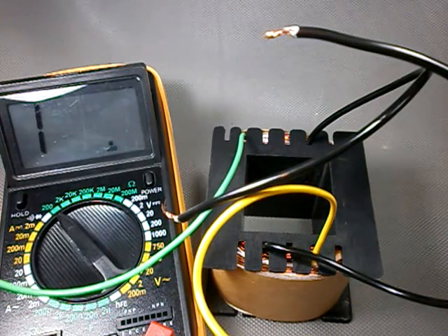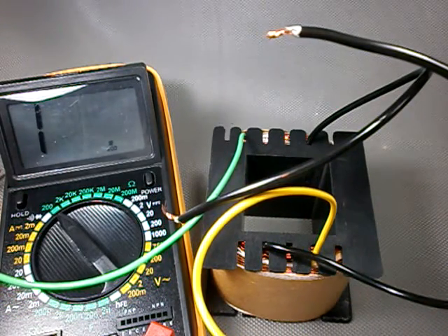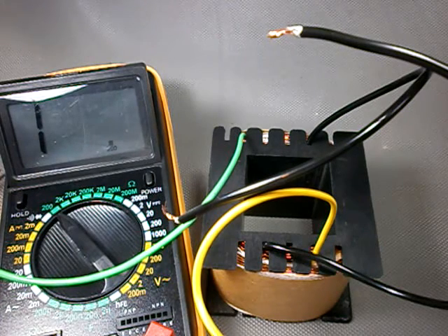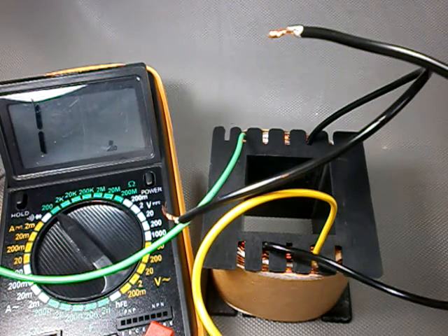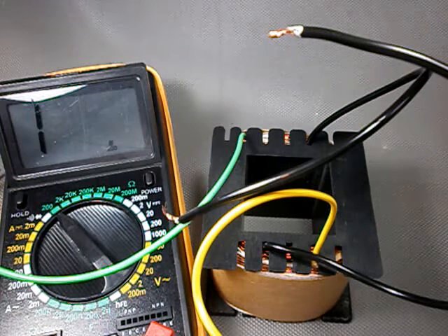It is important that you test all the windings for insulation and continuity before installing the core. If something is wrong, you just rewind the problematic winding. Otherwise you will have to do the tedious and time-consuming task of disassembling and reassembling the core again.